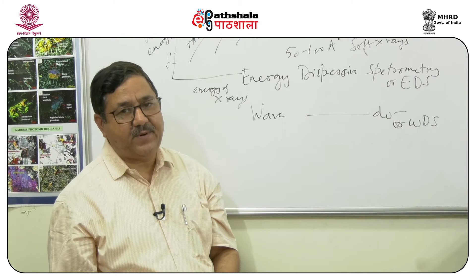Since there is a range of energies or wavelengths to be measured, one diffracting crystal is not sufficient. That is why there are several possible crystals. For some elements, more than one crystal overlaps, which means that an element can be measured using two different kinds of diffracting crystals. Which to choose? The decision is based on the higher resolution achieved by a particular crystal.